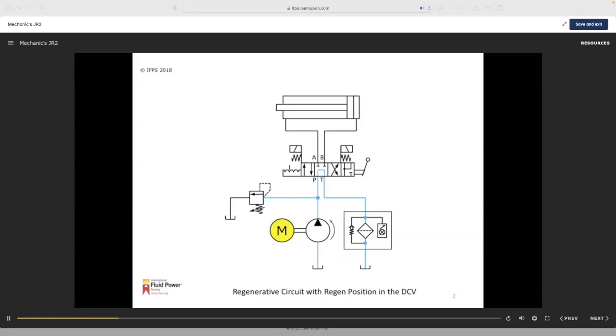A manual operator can select the detented regen fourth position. The manual position puts the spool in a regeneration mode. All the oil leaves the rod side and joins the pump flow going into the cap. If the rod end area is half the piston area, the cylinder speed will double. There is no flow going back to tank.